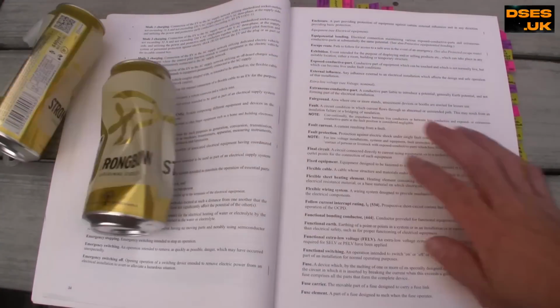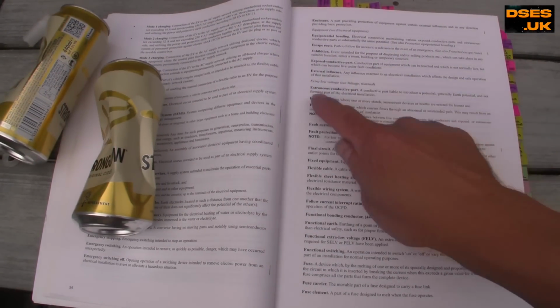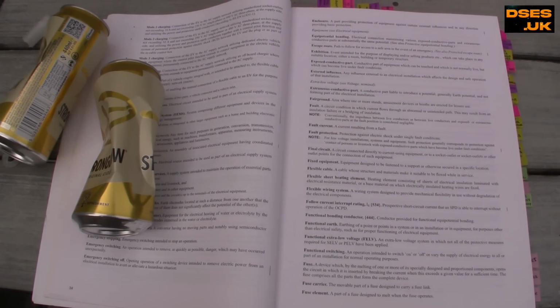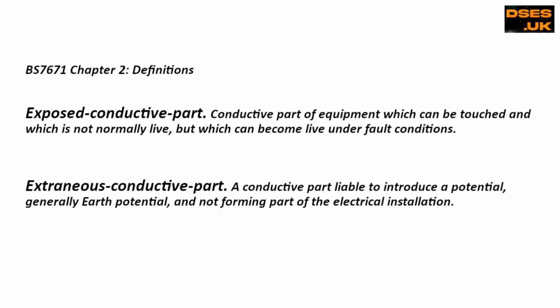When I talk about conductive parts, they'll either be exposed or extraneous. Looking in BS 7671 Chapter 2 definitions, exposed parts are things like my metal switch and metal knockout box, conductive items that are part of the electrical installation, which ought to be at 0 volts under non-fault conditions, but may raise in potential in the event of a fault. Extraneous conductive parts would be something like a radiator or metallic gas pipes, nothing to do with the electrical installation, but nonetheless electrically conductive.